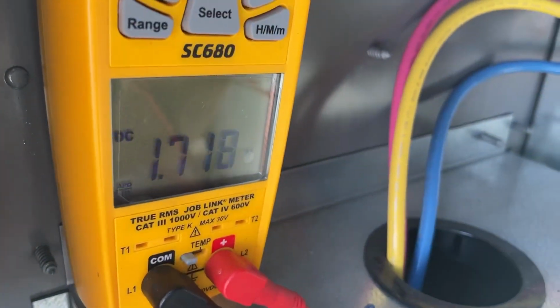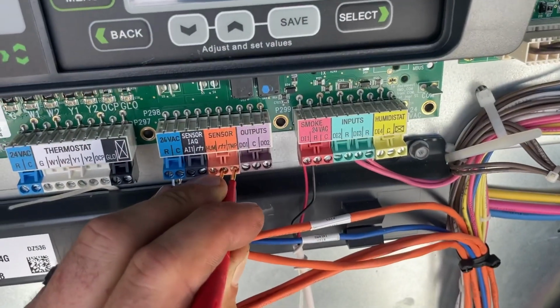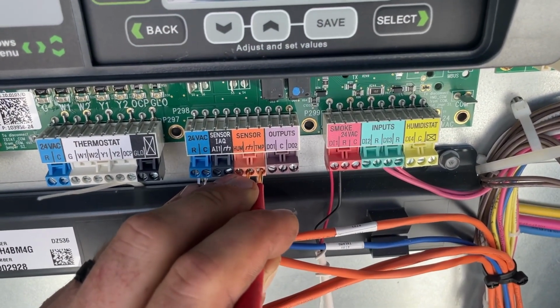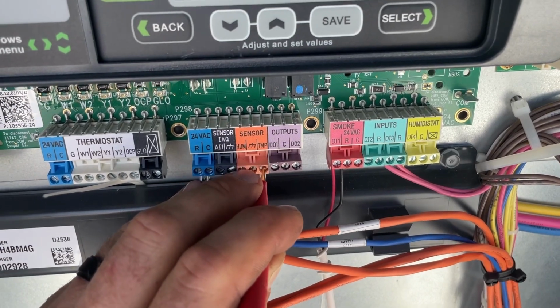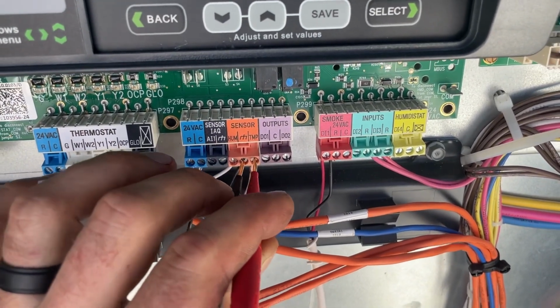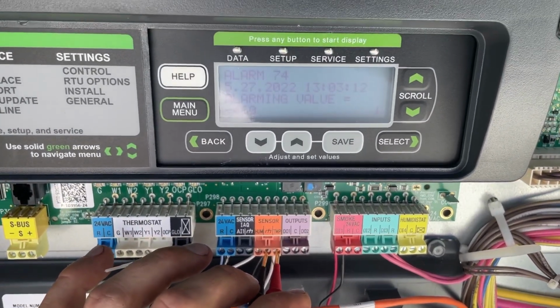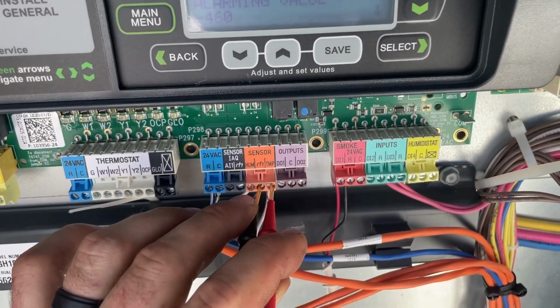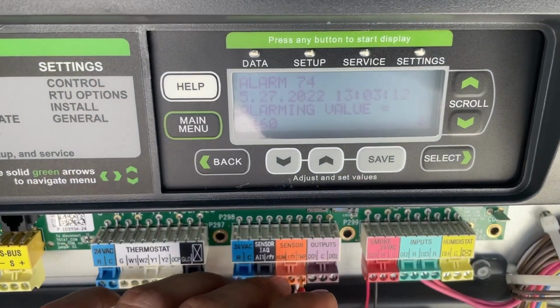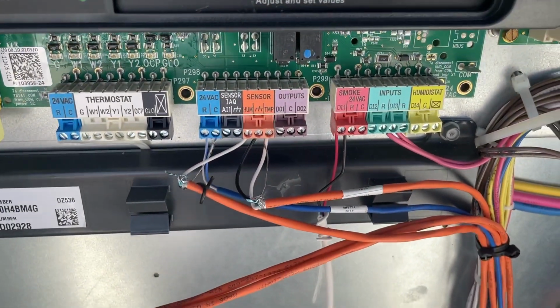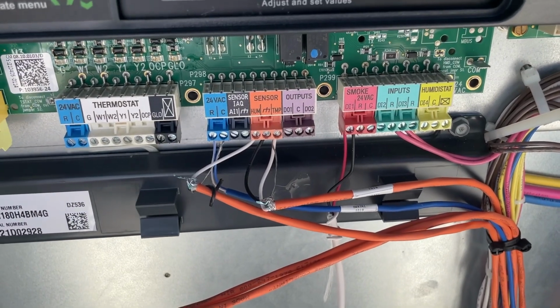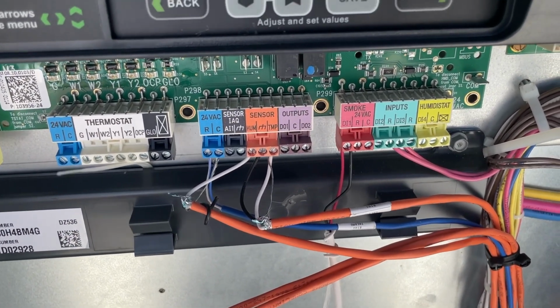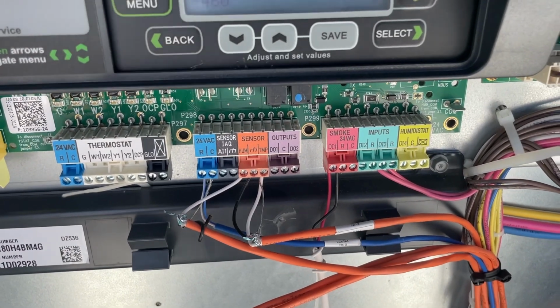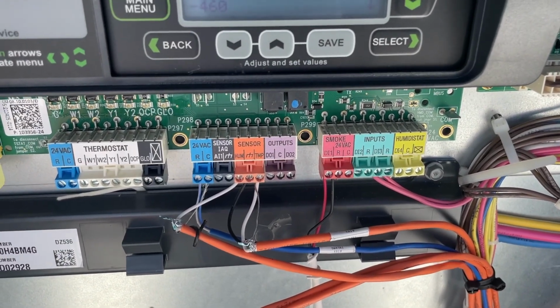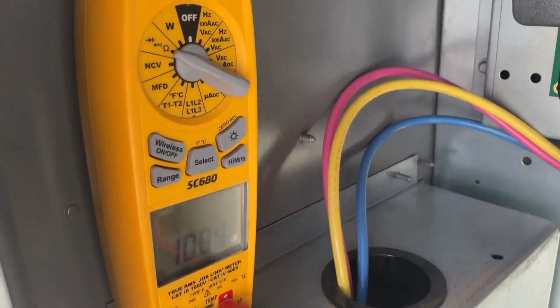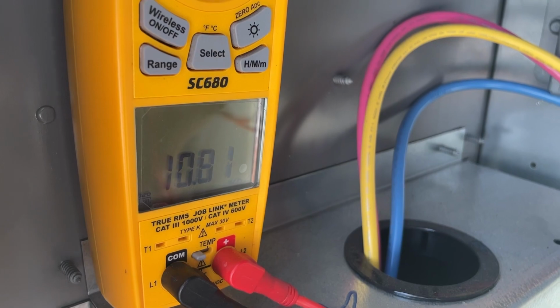See that? So you can't damage these circuits by shorting them. All you're doing is just dropping the voltage over the resistor. And that resistor is not flowing much current at all. It's a very high value. And based on the fact that the voltage was half, and this sensor is a 10K, at 77 degrees, which is 25C, that means it should be reading right about 10K right now, and maybe we'll look at that too. I would guess that the resistor on the board is actually at 10K as well. All right, so I'm just connected across those wires, and you can see I've got about 10K.